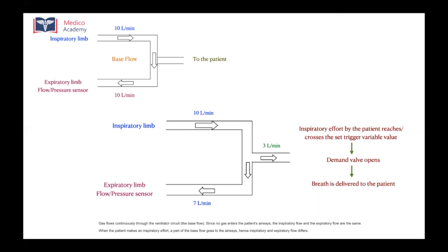So it is either a change in the base flow or a drop in the base pressure which acts as a trigger for delivering a mechanical ventilator breath to the patient. That is something which you need to set. If you keep very high triggers such as 5, 7 or 8 centimeters of water, the patient will have to generate very, very high flows, which will in fact increase the work of breathing, and the patient will get tired. The patient is already tired. Someone who comes in respiratory failure, you're basically putting the patient on the ventilator to give rest to his respiratory muscles. So you shouldn't keep very high trigger values.